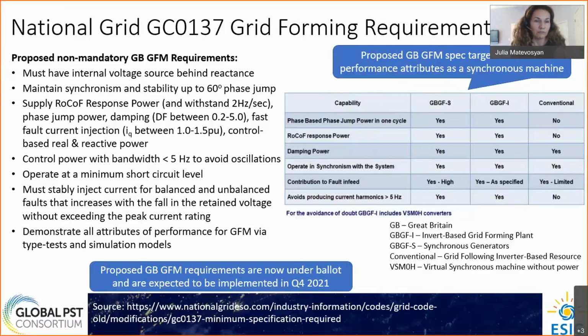And again, the resource providing this grid forming capability should act as an internal voltage source behind reactance, should maintain synchronism stability up to 60 degrees phase jump, and supply rate of change of frequency power. So what this means, initially it was separate inertial power and frequency response, but then to make it broader and allow application of grid forming inverters that don't have virtual inertia, this was converted into this rate of change of frequency response power. So that would include inertial response and frequency response capability. And so a resource would have to describe what capability they have, and they would be valued accordingly depending on how this market is designed.